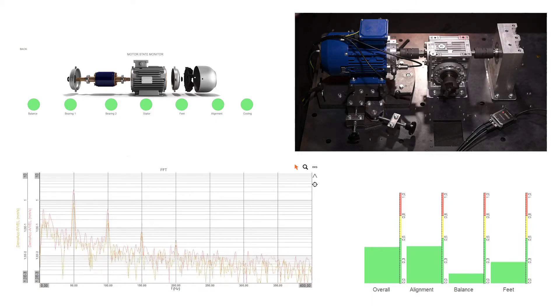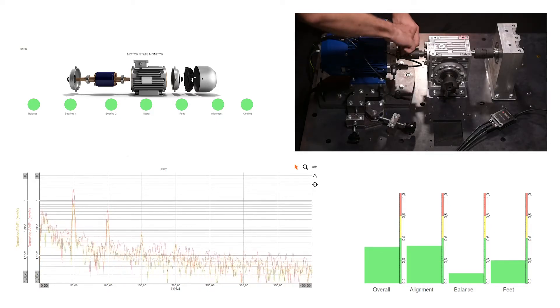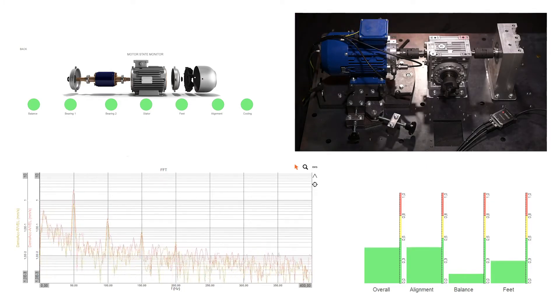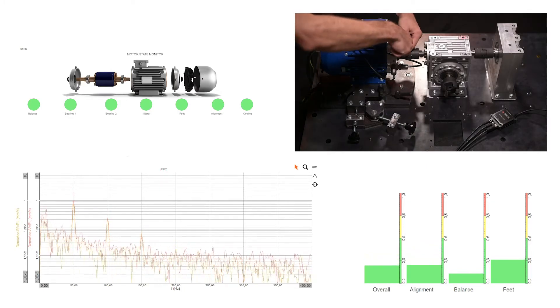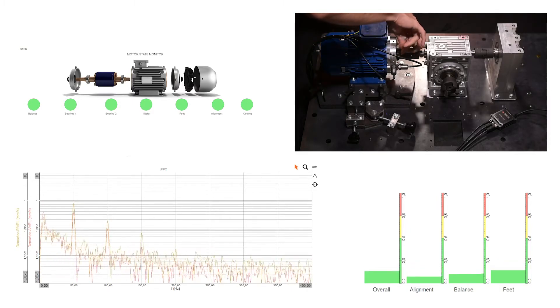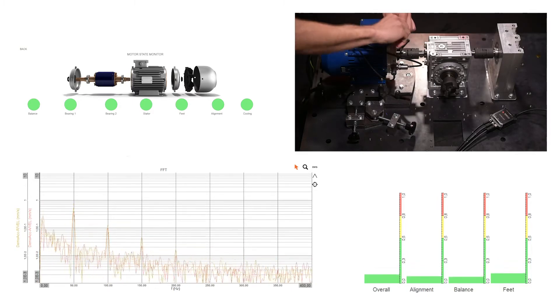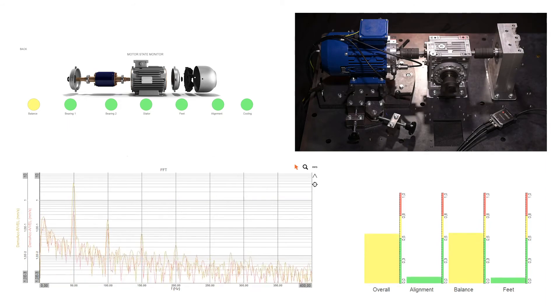Because we have a small motor with a flexible coupling, there are also significant levels of the second harmonic in axial direction. To simulate the imbalance, we will add a mass of 5 g on the outer side of the coupling by changing the coupling screw with a longer and heavier one. This will move the center of mass away from the shaft centerline and will cause higher vibration at the frequency of the motor rotational speed in radial direction.